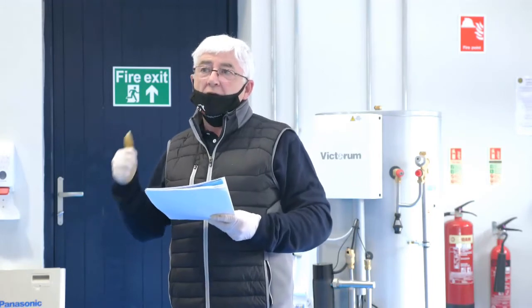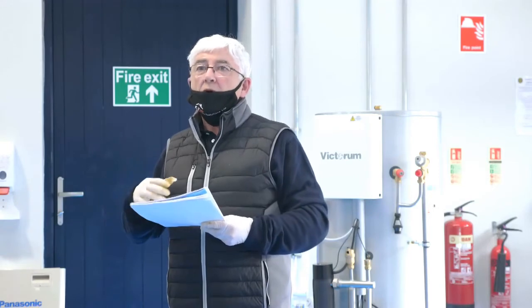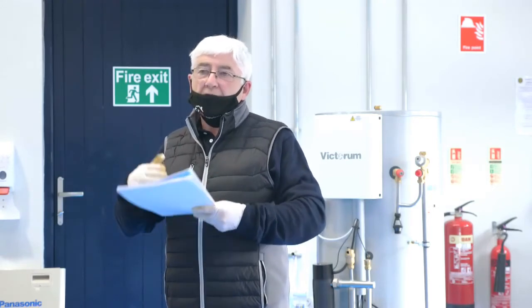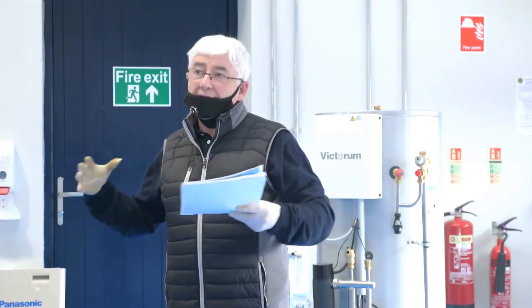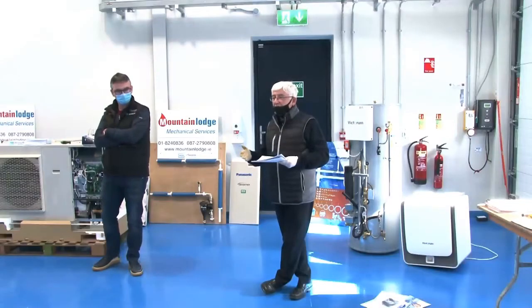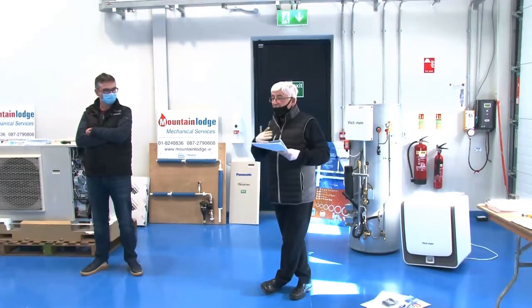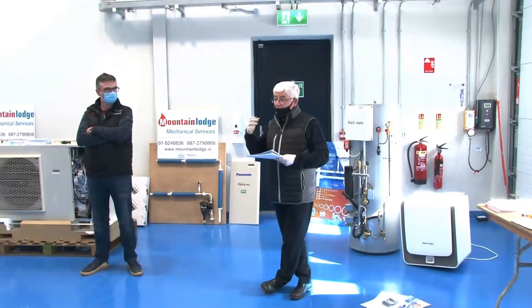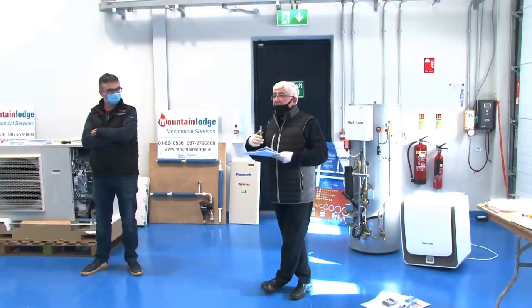They're impermeable to oxygen, which is a very important thing. 100% impermeable to oxygen, whereas most plastic pipes, even with resin barriers, will allow a small amount of oxygen to penetrate the wall of the pipe, which can lead over time to corrosion in systems. Now they don't, and it's been proven. I've sold Qualtex pipe for years myself. We've sold a barrier pipe, and 25 years on there isn't a lot of feedback coming back that it's causing problems in systems, you know what I mean?